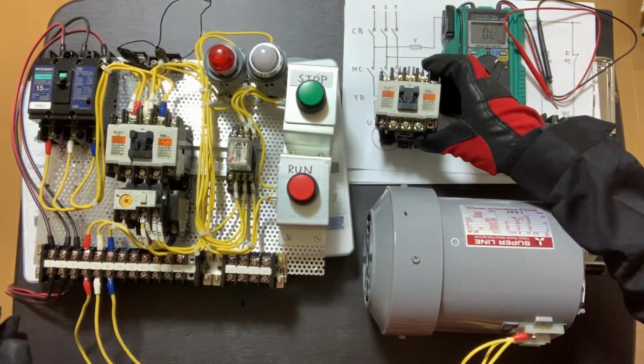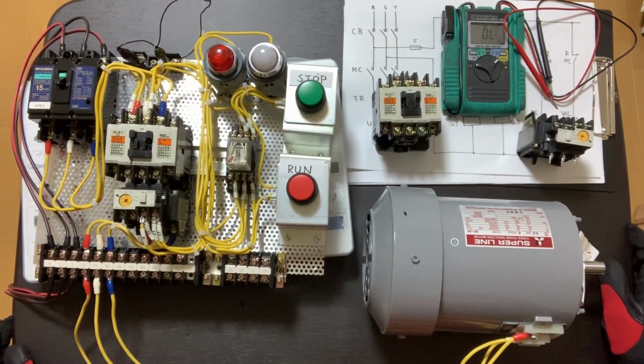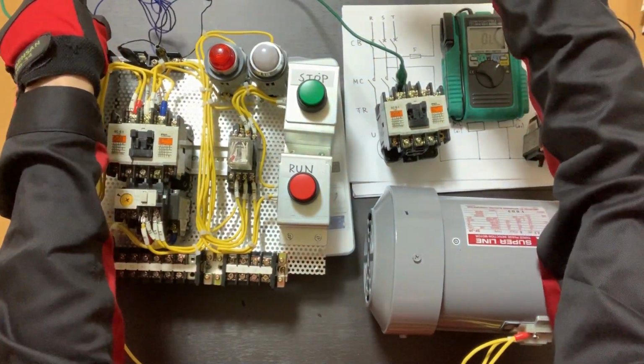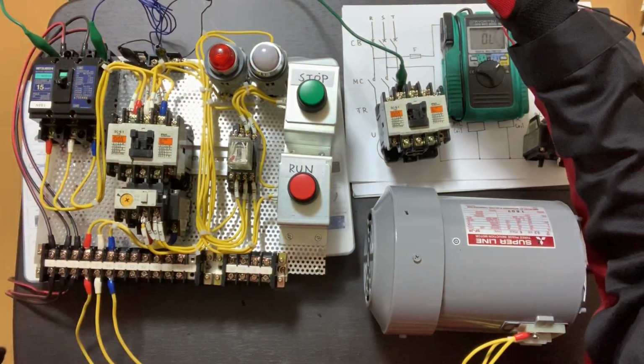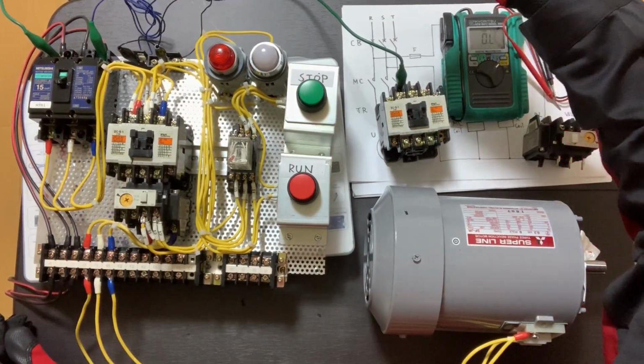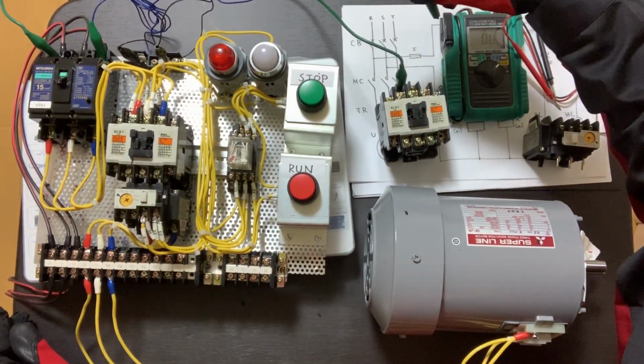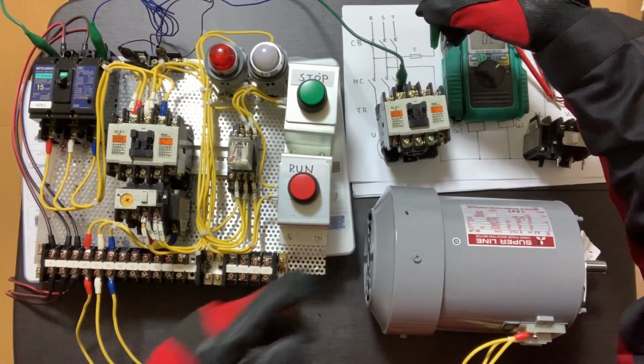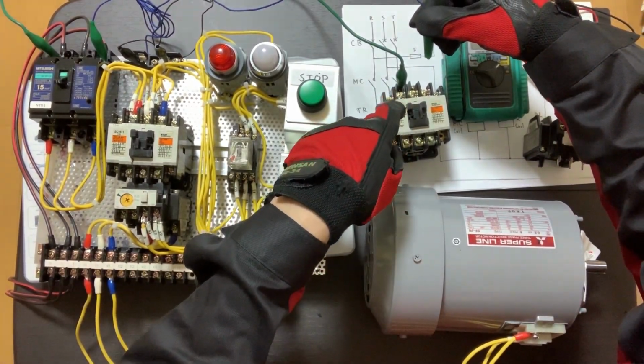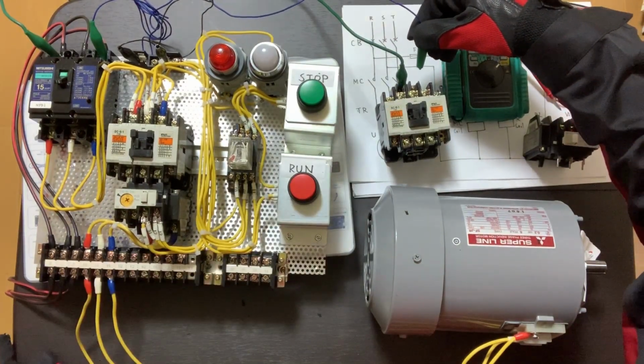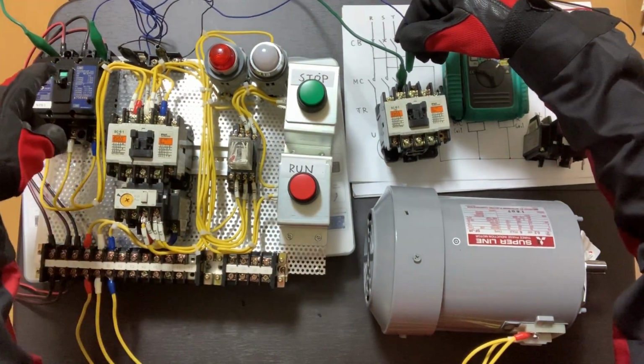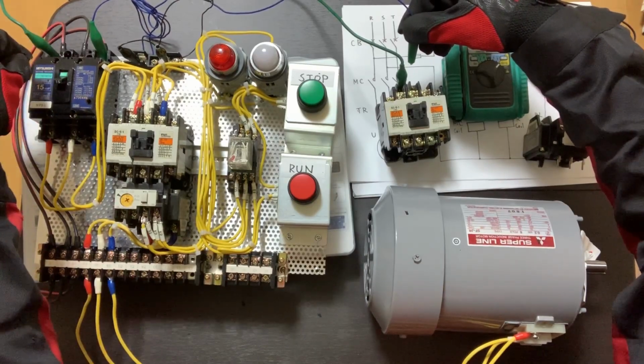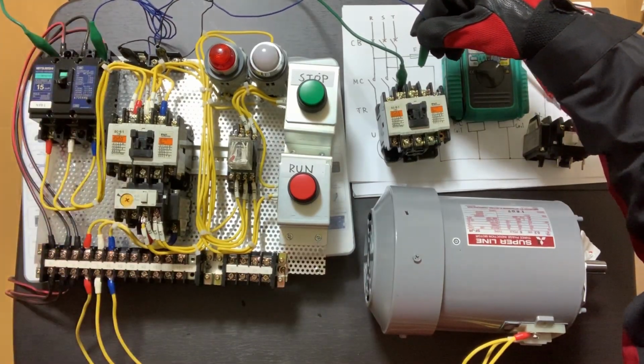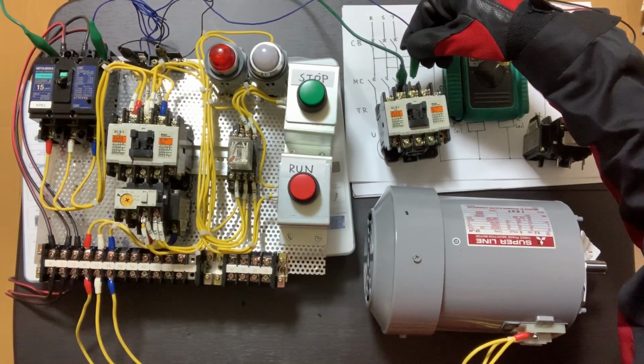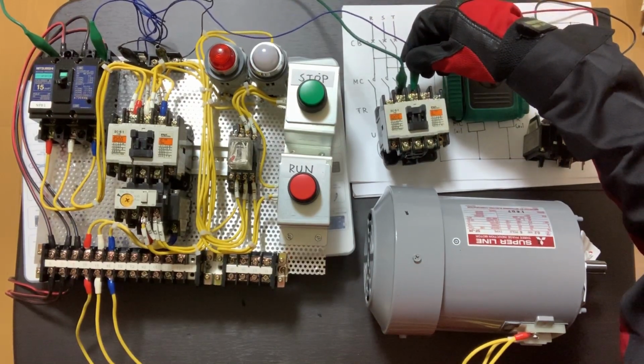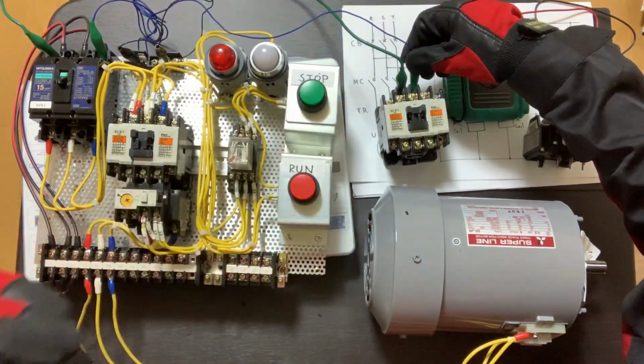So let me show the practical motion. Alright, be careful. Let me try the actual motion of the magnetic contactor. I try to apply rated voltage to the coil terminal by supplying from the primary side of 200 volt. Alright, 3, 2, 1. It's energized like this and de-energized.